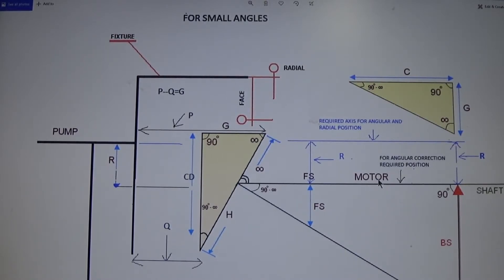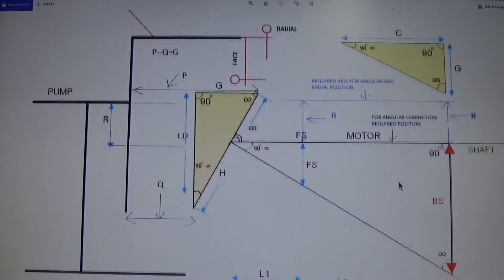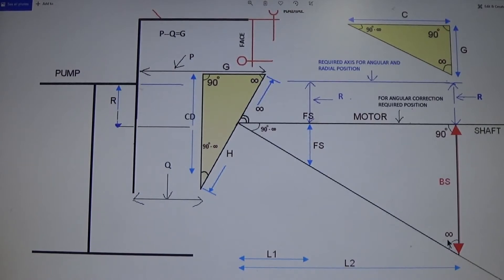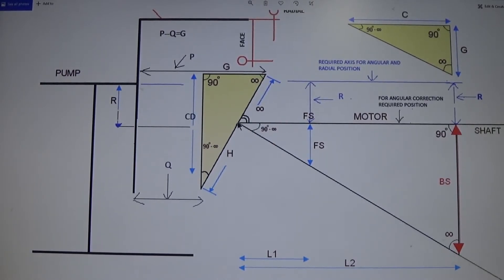Where you will be adding or removing the shims: FS is the front side, and you can see in this figure that you need to add shims here. BS is the back support. In this position of the motor, you will need to add shims equal to BS. L1 is the distance from the coupling face to the front support, and L2 is the distance from the coupling hub face to the back support.